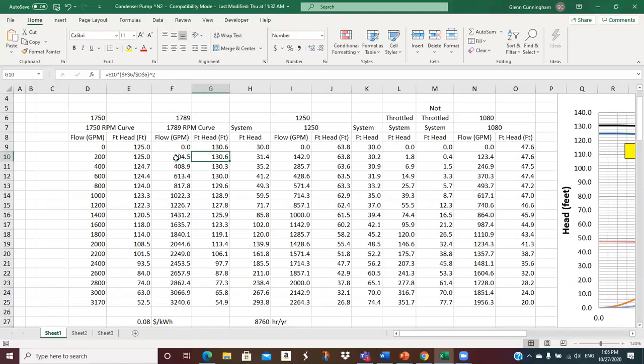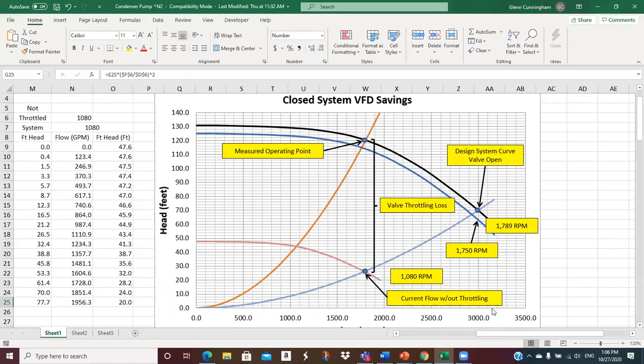When I translate head, though, the head translates as the second power. So I take that same speed ratio and I square it, and then I multiply it by the 125 feet times this divided by this squared, and it translates the head to 130.6. And then, so that gets copied all the way down. So all of these, this is the speed ratio times whatever the flow is here. So 3170 at this higher speed will translate into 3240.6. And this 52.5 translates into 54.9. So I've translated all of these points over to operation at 1789. And then I plot that curve.